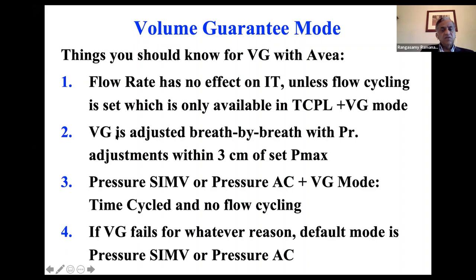VG is adjusted breath-by-breath with pressure adjustments within 3 centimeters of the maximum pressure you set. Pressure SIMV or pressure assist control plus VG mode is time-cycled with no flow cycling. If you want flow cycling, use TCPL plus VG mode. That's why I use TCPL plus VG in my unit, although there is nothing wrong with using SIMV or pressure AC combined with VG mode.